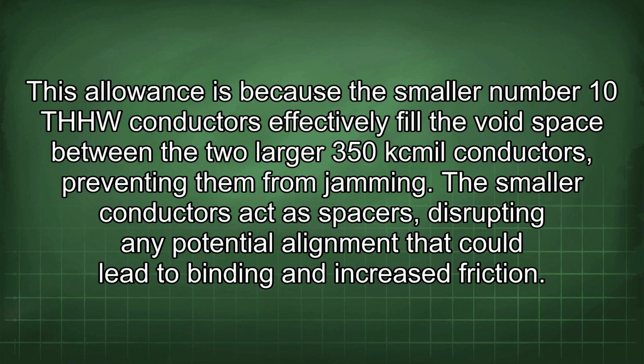This allowance is because the smaller number 10 THHW conductors effectively fill the void space between the 2 larger 350 kcmil conductors, preventing them from jamming. The smaller conductors act as spacers, disrupting any potential alignment that could lead to binding and increased friction.